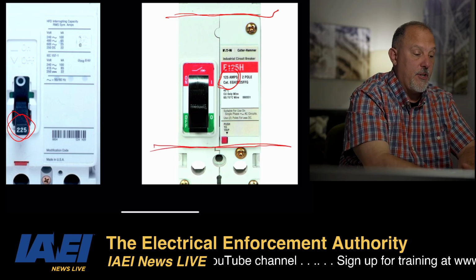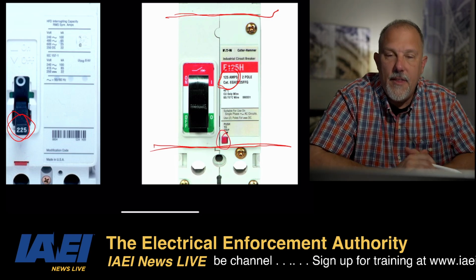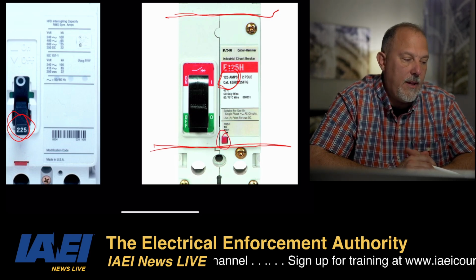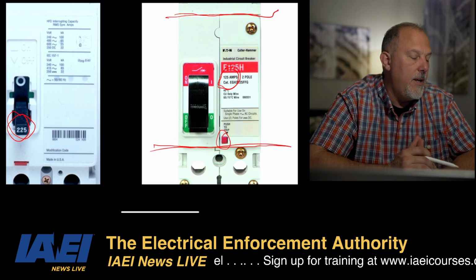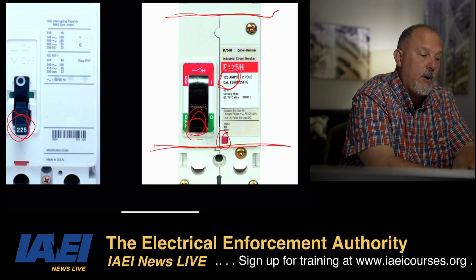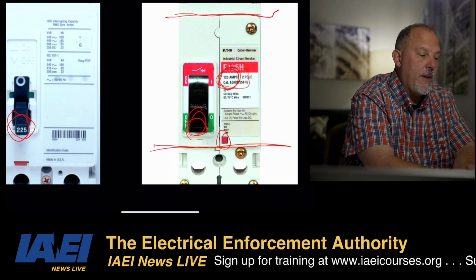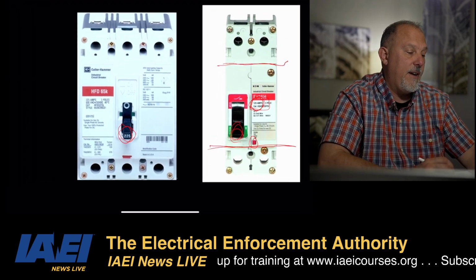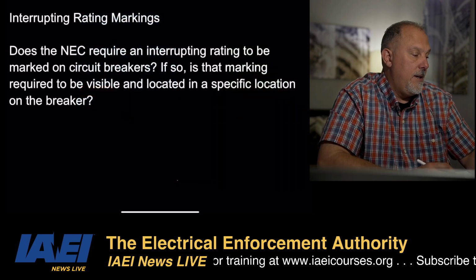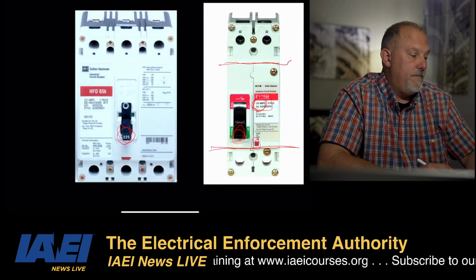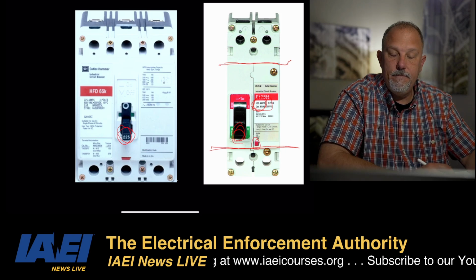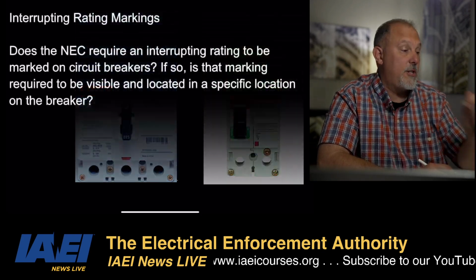It would have to, because you have a push to trip button. So that's all visible. All of that whole label is visible through the dead front. But you'll notice it's not on the handle at all. It's over here on the label. And it's 125, so it's not required to be in that location. All right, let's move to the next question.